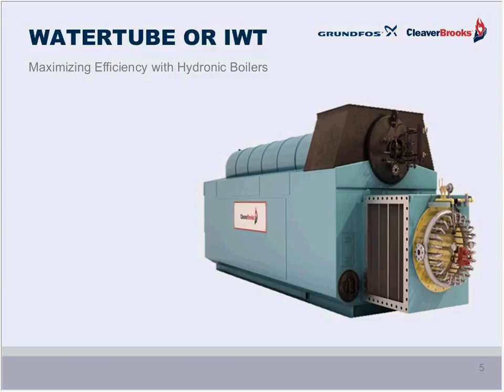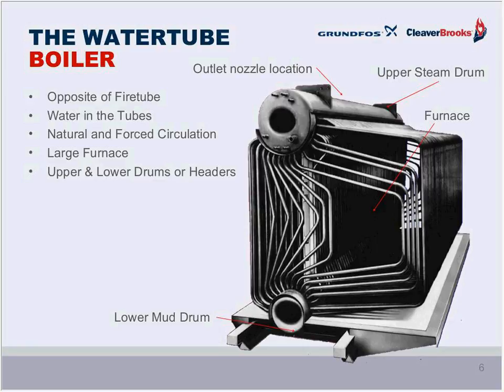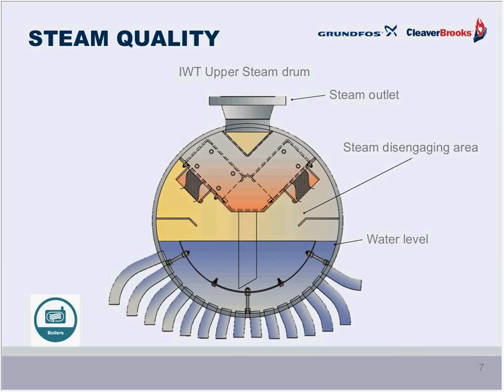Starting then with the industrial water tube, also known as the IWT, you'll recall how the pressure vessel is basically constructed with the water-filled tubes emanating from the lower mud drum, as we call it, and connecting to the upper steam drum where the mix of steam and water are discharged. Now, looking at the steam drum in this industrial water tube boiler more closely, you see the approximate water level that we need to maintain in order to provide safe and reliable service. And also note the steam disengaging or the steam storage area where the steam accumulates as the evaporation of the water takes place. And then once the steam is formed, it exits through the steam outlet to the connected steam header, which then leads to the process and/or the heating load in the facility.